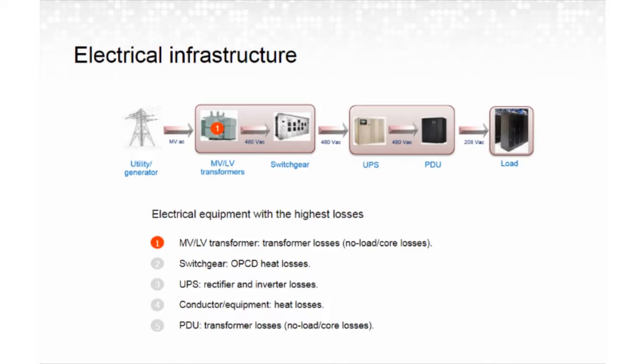Thank you, Ken. As mentioned, transformers are part of every electrical system. And as seen in the graphic, the medium voltage to low voltage transformer at the building service is the first opportunity for energy losses. Additional transformers to step down from 480 to 208 volt are not shown in this graphic, but as we know, they occur many times in a building.